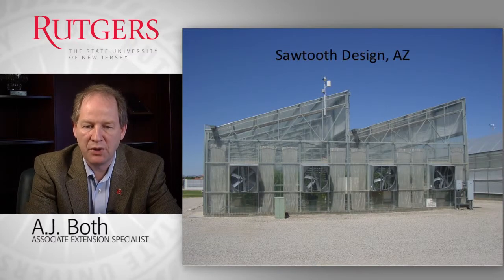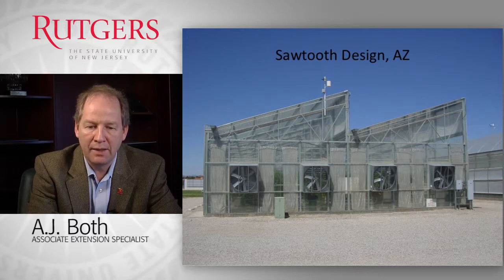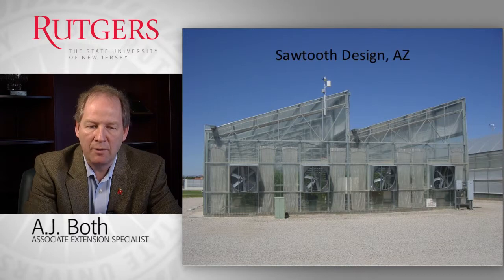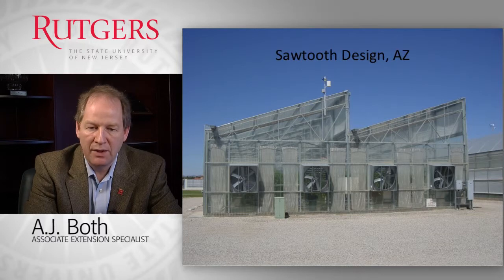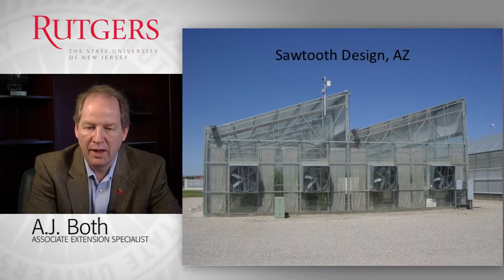In some cases we see this very special sawtooth greenhouse design in Arizona, which we like for warmer climates where we can use prevailing wind directions to improve ventilation. If the prevailing wind direction is coming from our left and blowing to the right, the air goes over the greenhouse roof and just as it detaches from the peak, it creates an area of low pressure and turbulence that helps suck out the warmer air inside. By designing this particular roof structure, we can improve the ventilation and provide better growing conditions for the plants.